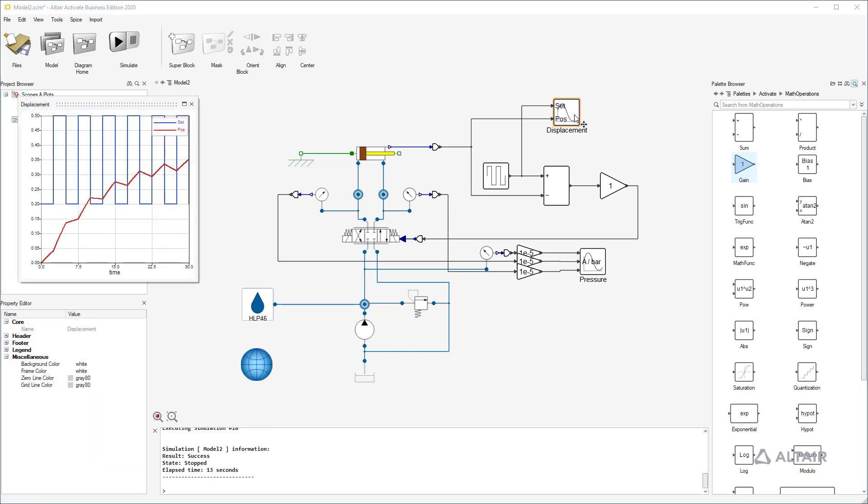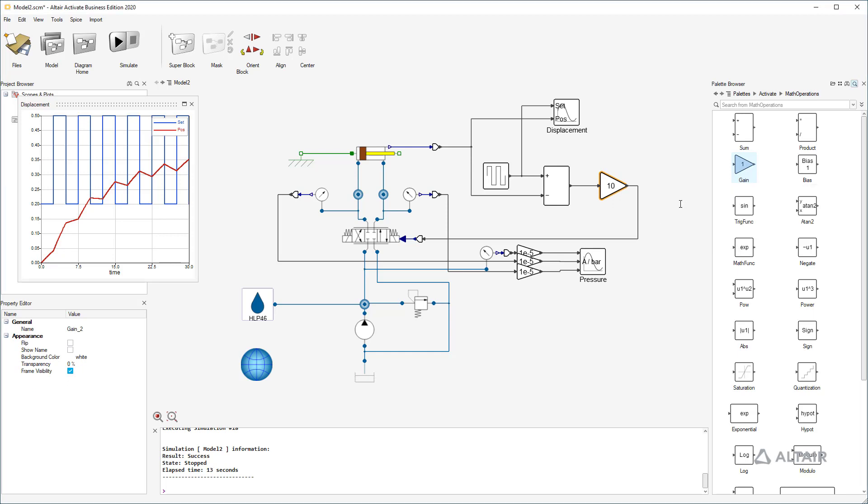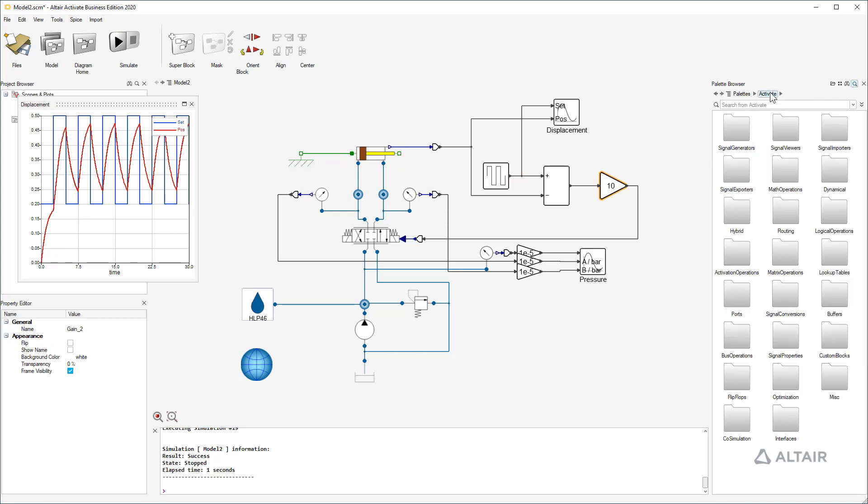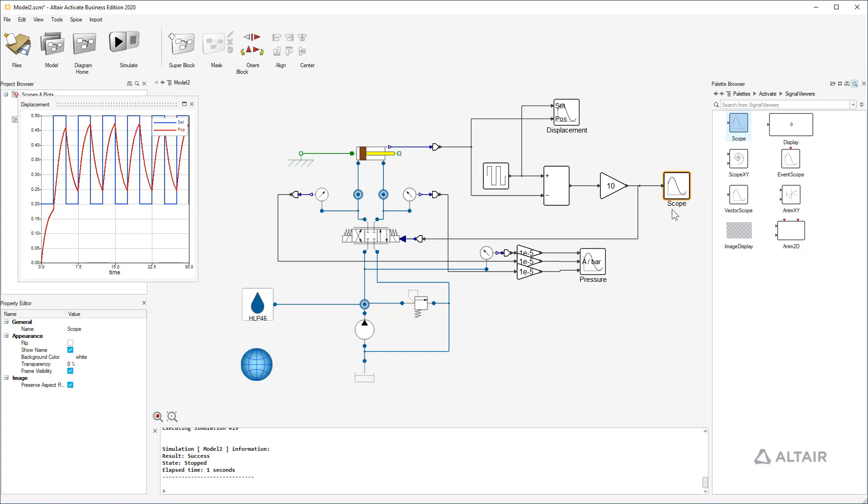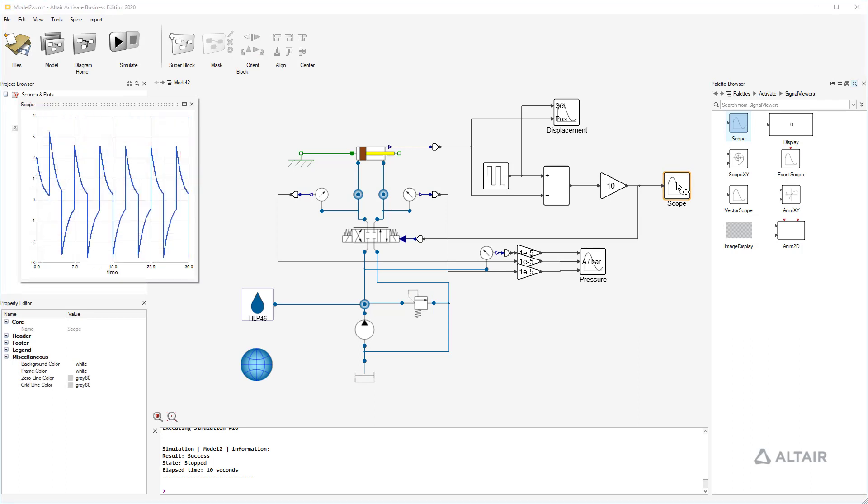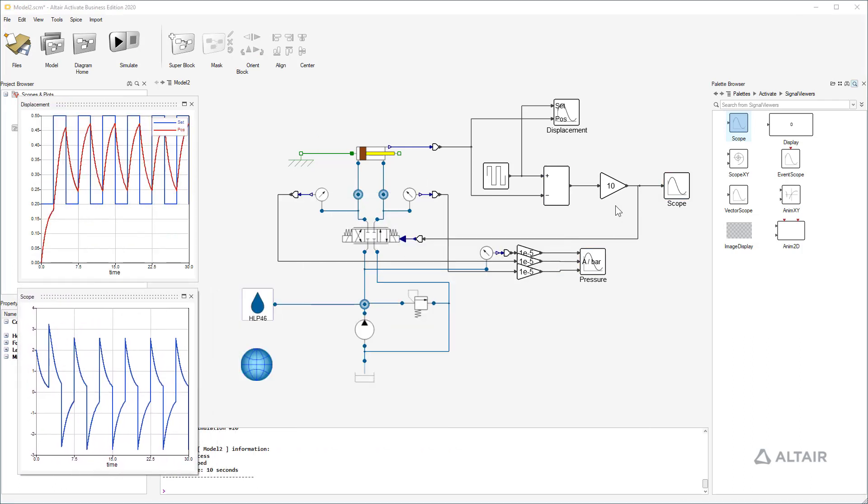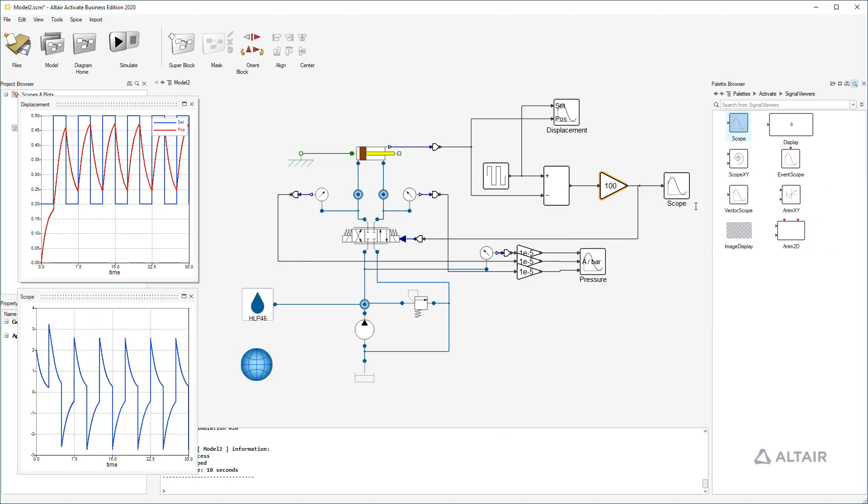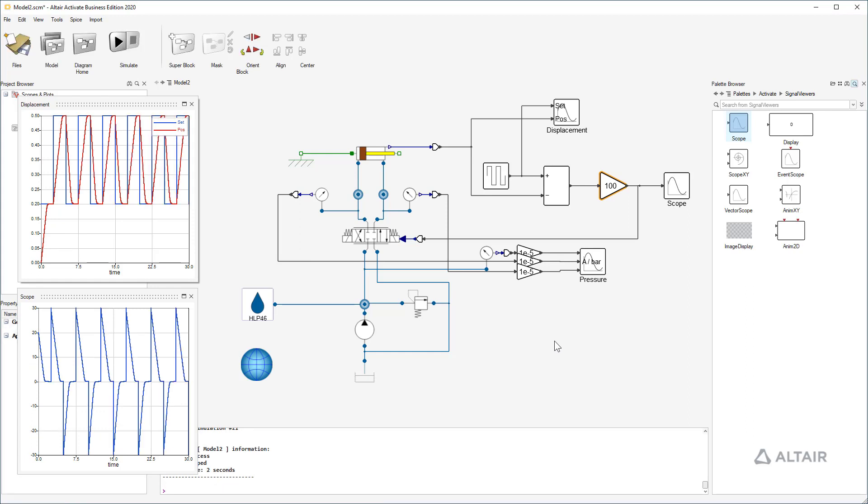No, the cylinder doesn't reach the desired position. Let's increase the proportional factor to 10. It's getting better, but that can't be all. Let's have a look to the valve signal. If it's less than 10, there is more potential in the system. And yes, we can increase the proportional factor again. Let's try 100. And now the cylinder moves with maximum speed and reaches the positions without any oscillation. Perfect.